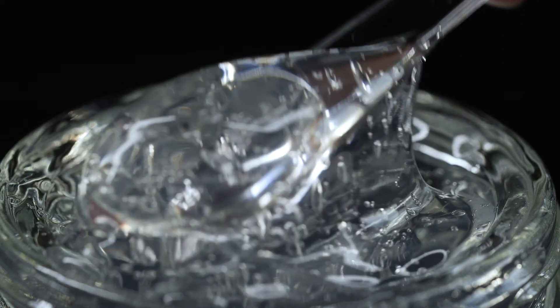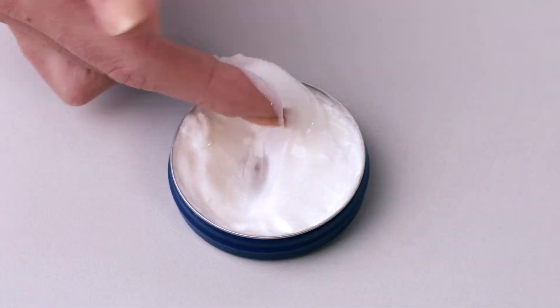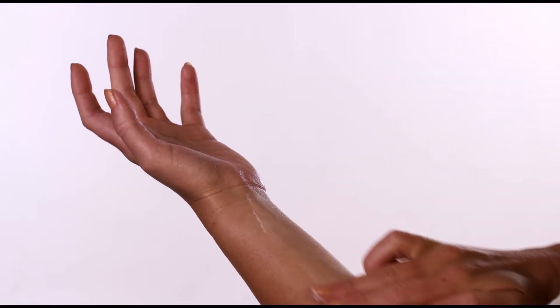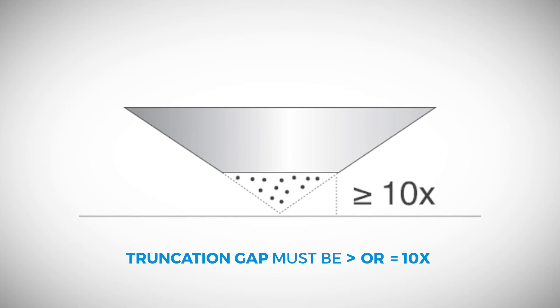A variety of samples may be tested with these geometries including gels, creams, lotions, toothpaste, as well as many others. For samples with particles, the truncation gap for the cone must be greater than or equal to 10 times the particle size. Parallel plates can accommodate larger particles because the gap height may be increased.